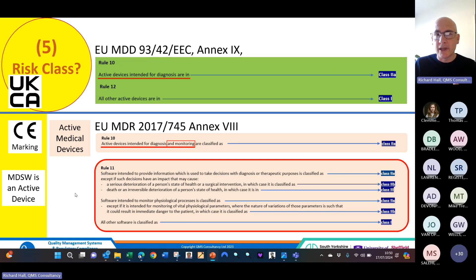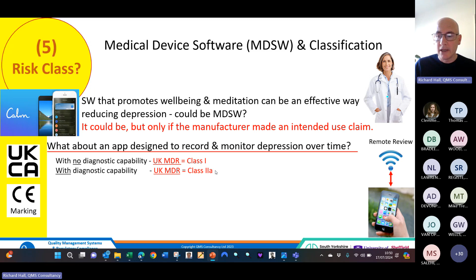So when we go back to this definition, we've got a device which is used to capture information about depression. Then in the UK, this would be a class 1 device. Only if we were then doing some kind of diagnosis would it be classified as a 2A and it would never go any higher. In Europe, because of this definition of Rule 11, we now get a situation where the same software in France, for example, would be classified as a 2A. However, if you are using the information to score the depression, then it would be a 2B. And if you're adapting treatment for depression with the app, then it will be a class 3 device.